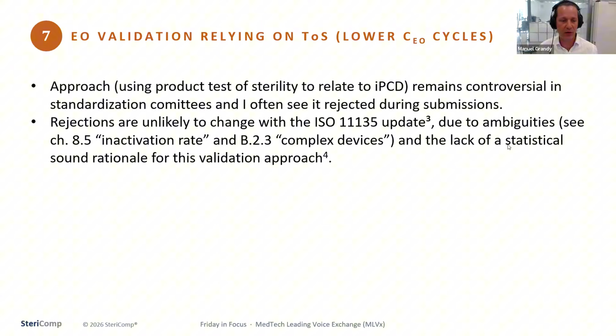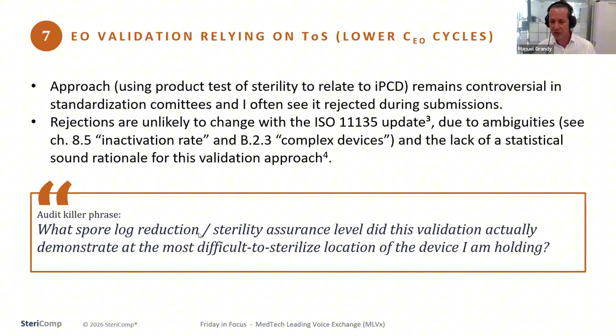What spore log reduction or sterility assurance level did this validation actually demonstrate at the most difficult to sterilize location of the device I'm holding? You're not able to tell at the most difficult to sterilize location what your SAL or your spore log reduction is, because you did not measure it with this method.